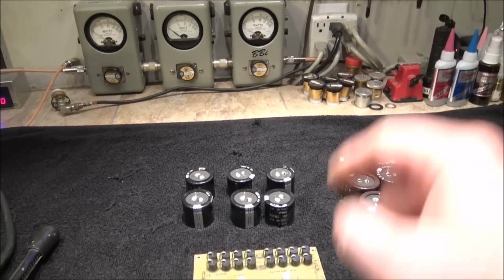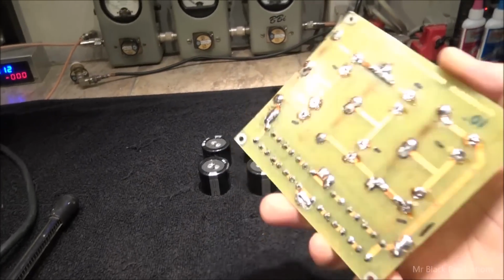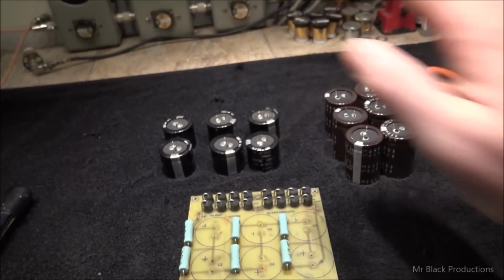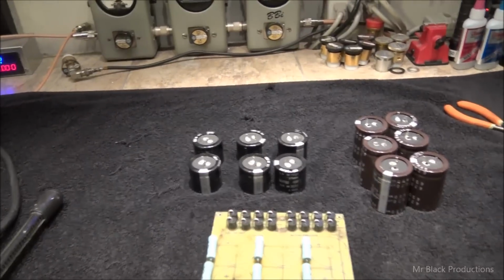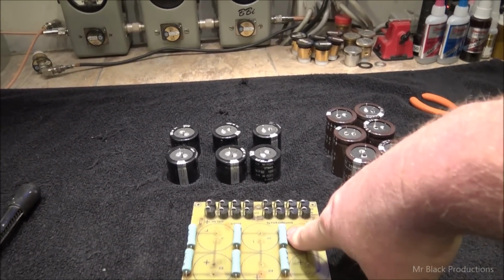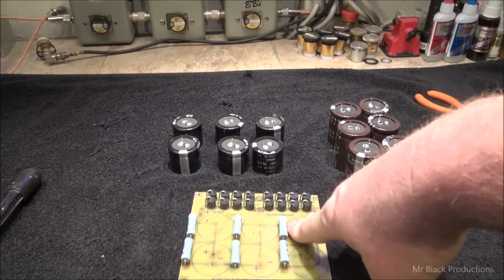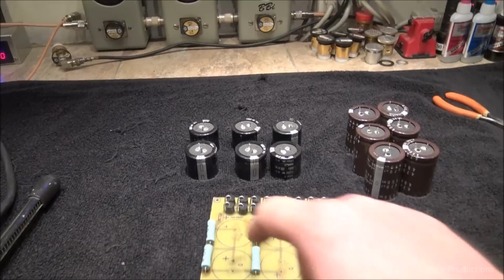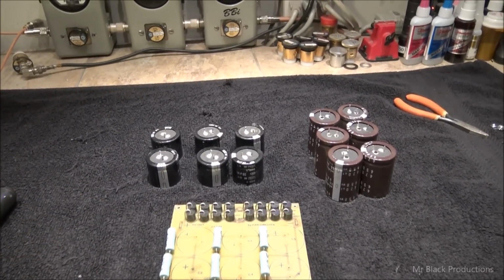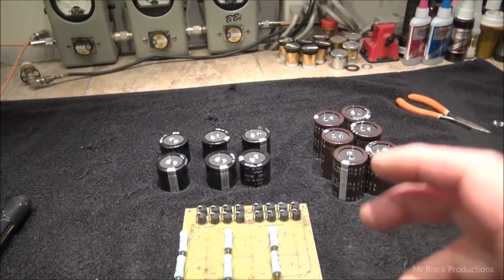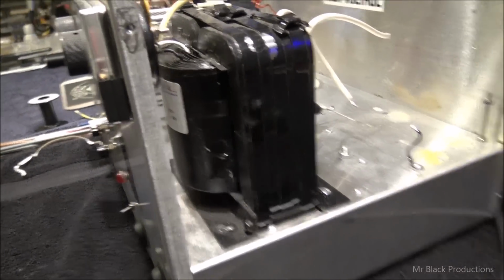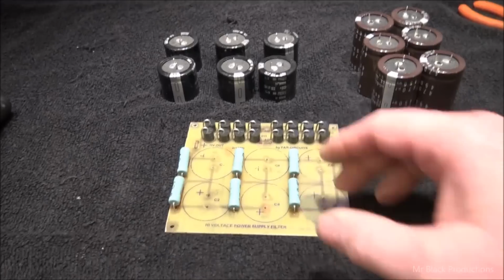So what we're going to do is I'm going to overhaul this rectifier board one more time. I'm going to put the little bit bigger caps in it. We're going to back up, because on the board it calls for 25K worth of resistance for the bleeders, which, when I do my load calculations on the power circuit, is a little high. It's constantly putting a load on the transformer, and we're going to see if we can get away from that. We're going to back this down.